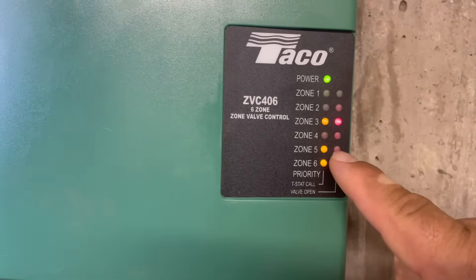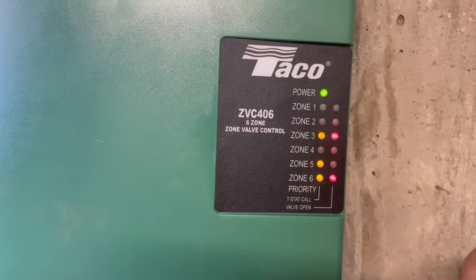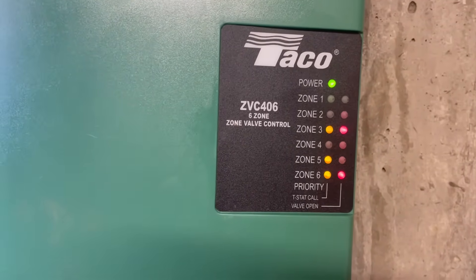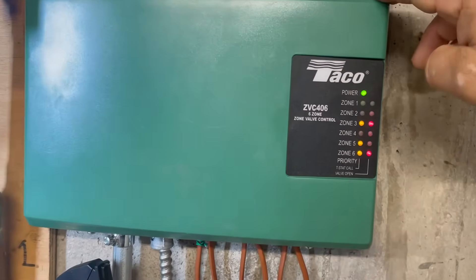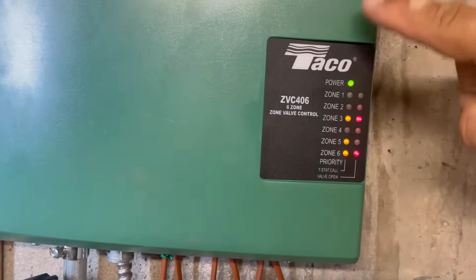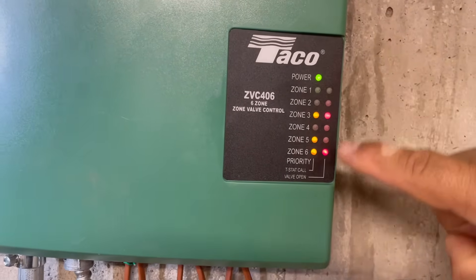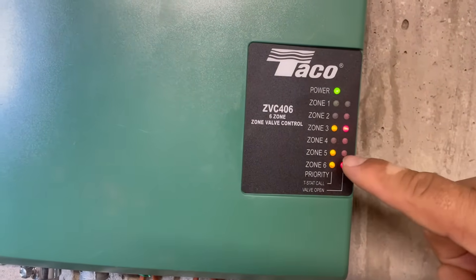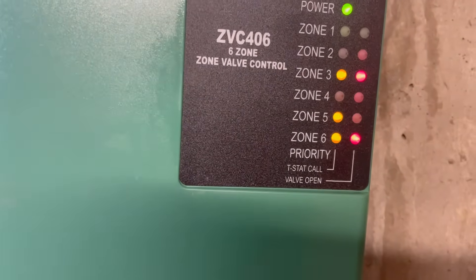Zone 5 is calling for heat, but the end switch is not activating the pump. So the valve is not opening. This is why I like this Taco control — if it's yellow it's calling for heat, and if it's red the valve is open. So on number 5, it's calling for heat but the valve is not open.